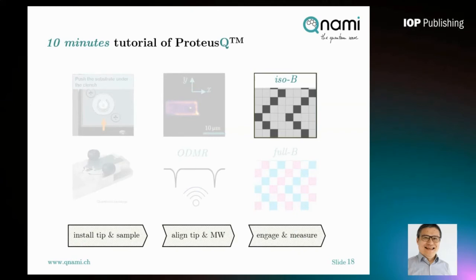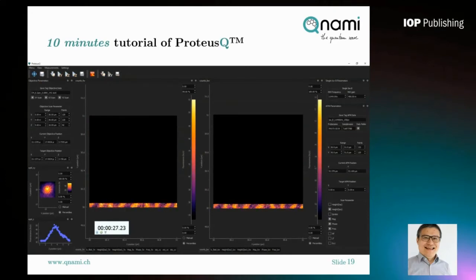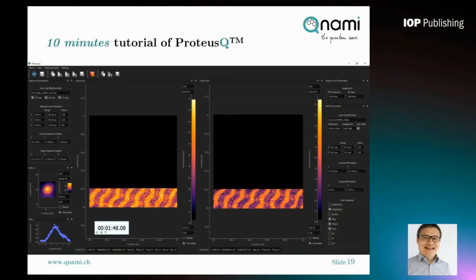We just need to land the tip on the sample surface and do scanning NV measurements using different modes. The first mode I'll show in the demo is iso-B mode. For the iso-B measurement, use the main interface of LabQ software and enter two important parameters in the iso-B measurement tab: the resonant frequency — the predetermined magnetic field component to measure — and the microwave power. By clicking the measurement button, you record both the forward and backward scan simultaneously, imaging both the fluorescence signal and topography information during the scan. It is always good to compare forward and backward scans to ensure no hysteresis in the sample scanner.